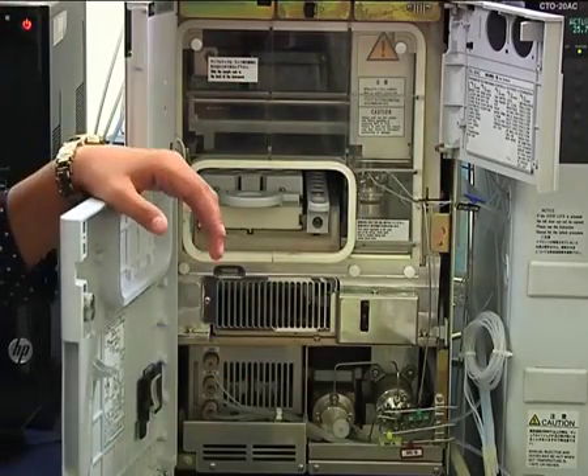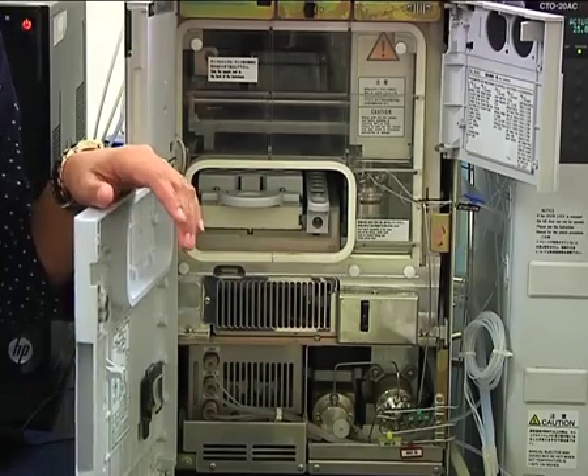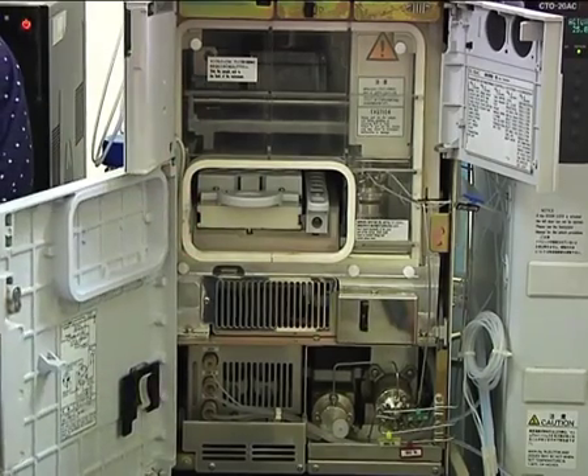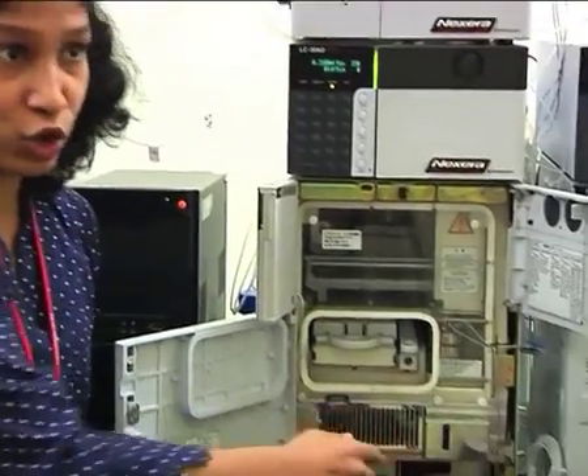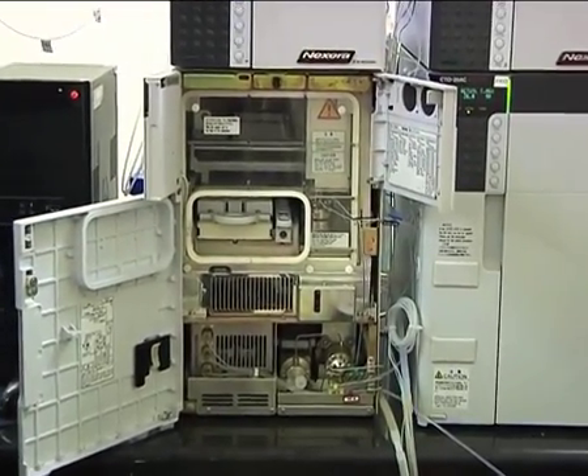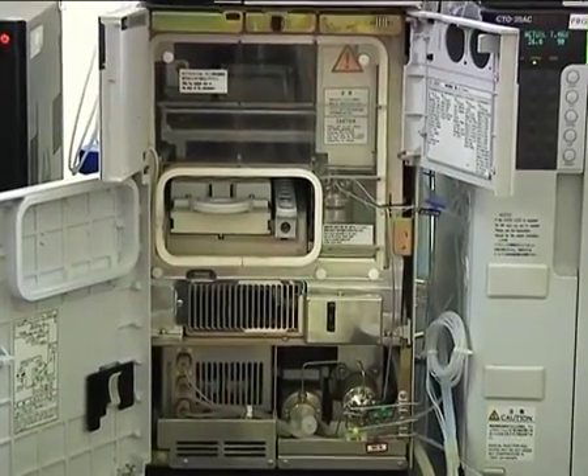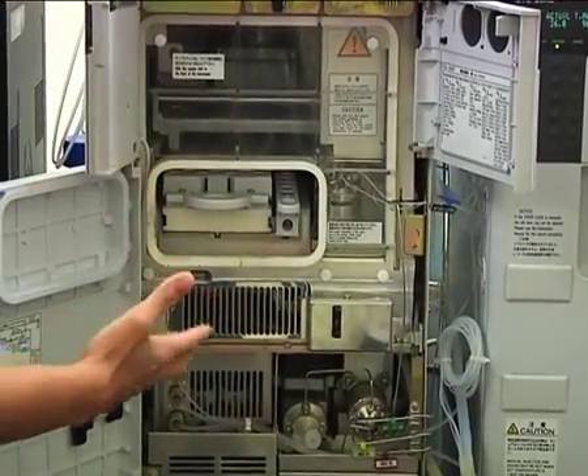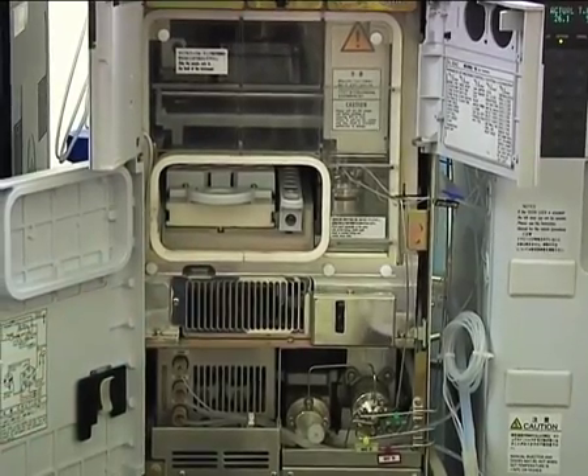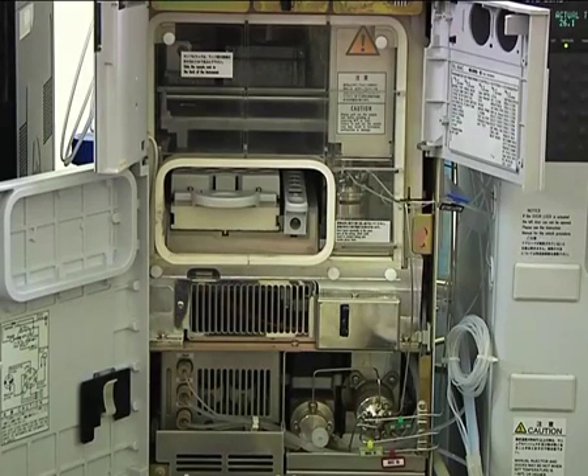Now what is the function of the low pressure valve? Suppose you have a manual injector. When you inject 2 different samples, in between the samples you perform rinsing of the needle or the syringe, so that there will not be cross contamination. When you are using an auto sampler, that function also needs to be done automatically, and that is the purpose of this low pressure valve. So in between the analyses, whatever rinsing happens, happens because of the low pressure valve. Now the feature of this auto sampler is that it gives you very low carryover, almost near zero carryover.